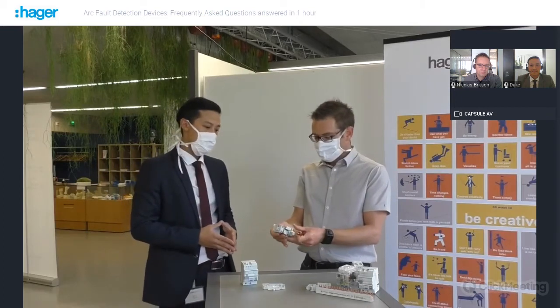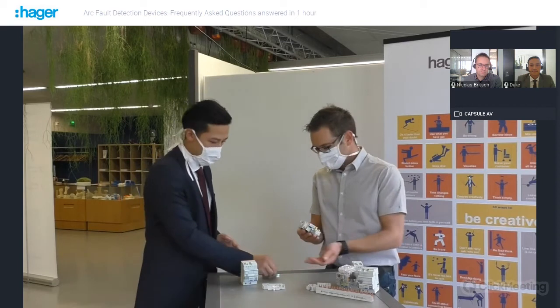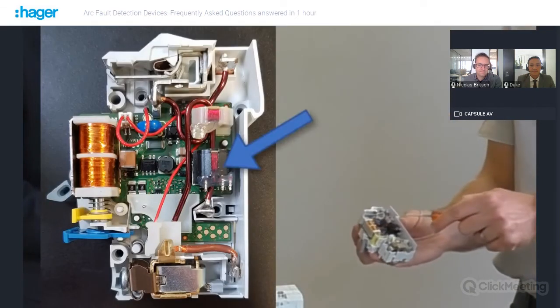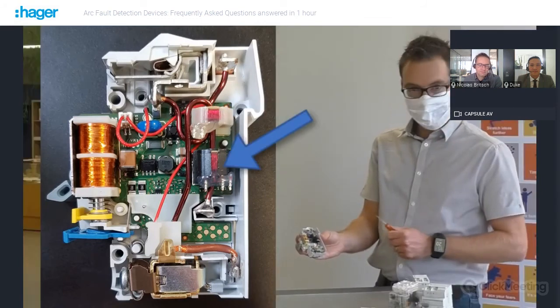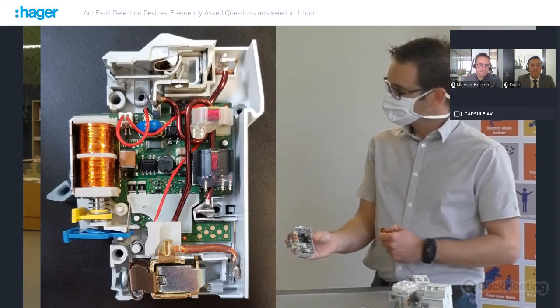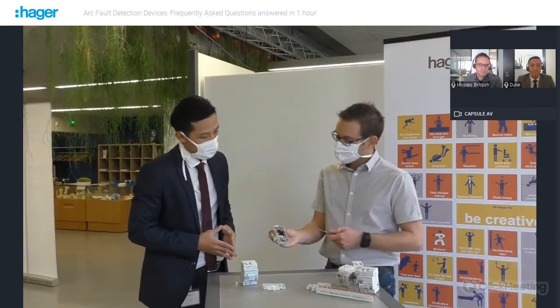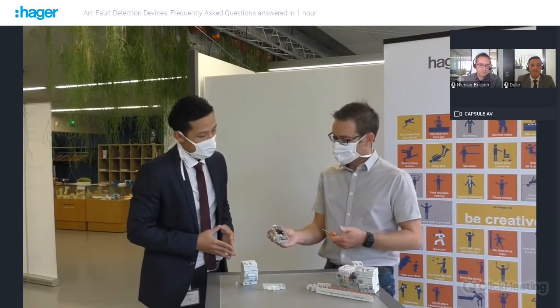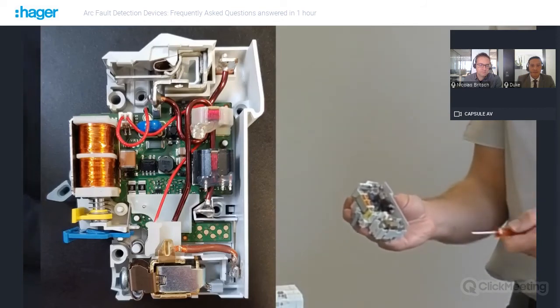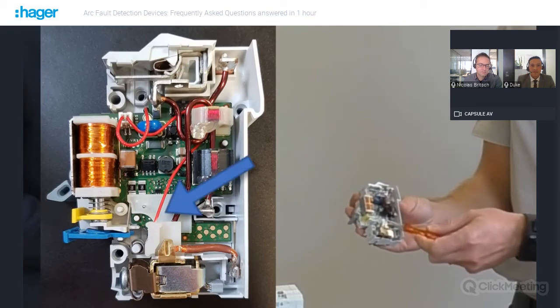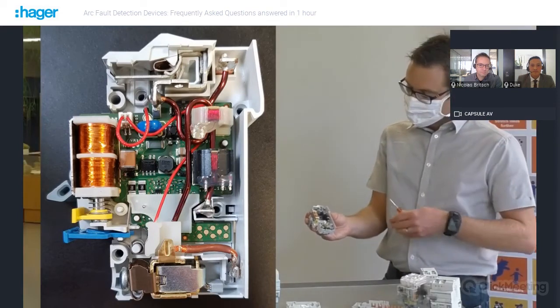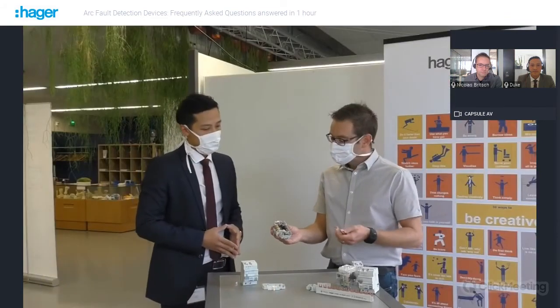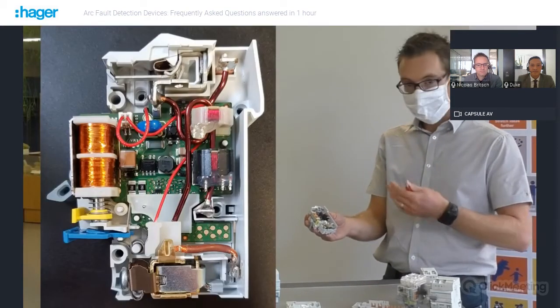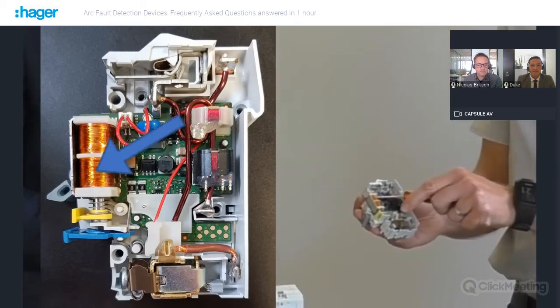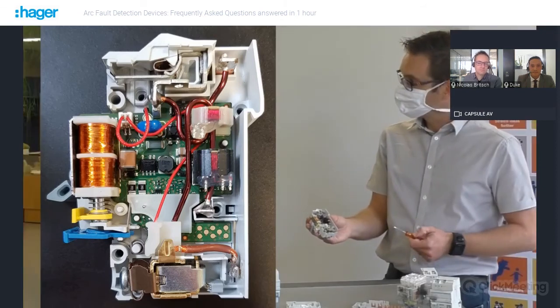And on the other side, here you have the arc fault part. On this side, the most important things are the current measurement cores. You have two cores. One is for the line current measurement, and the second is for residual current measurement. It's not a residual current protection, but it helps to analyze the circuit and the signals in order to perform arc fault protections. These two cores will produce electronic signals, and these signals will be measured by the microcontroller, which is located just behind this plastic part here. And the microcontroller will compute a lot of parameters, and it will decide if there is a dangerous situation related to arc faults. In this case, if the microcontroller identifies dangerous characteristics, it will actuate this component, the electromechanical actuator, and the product will open.